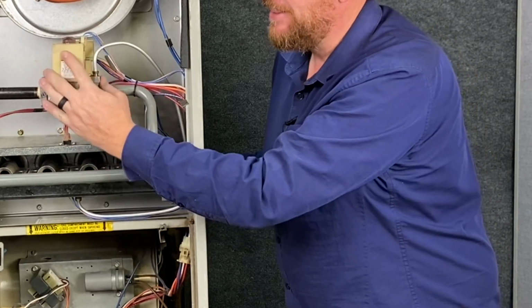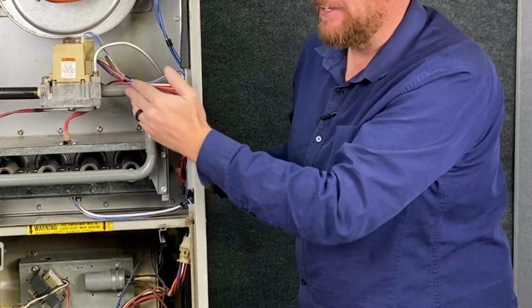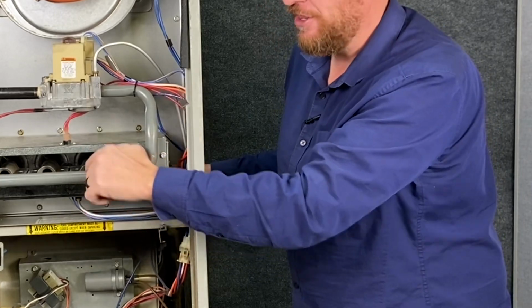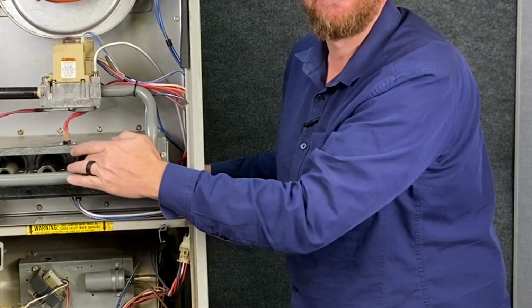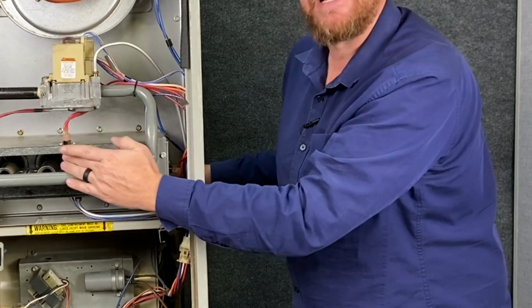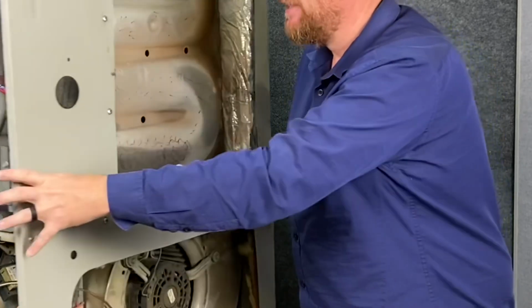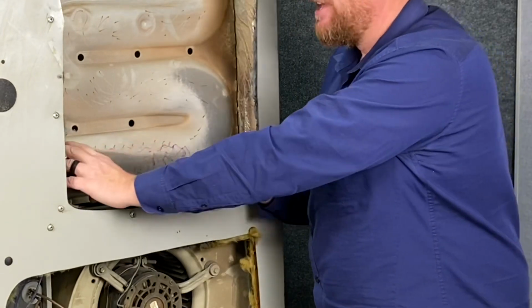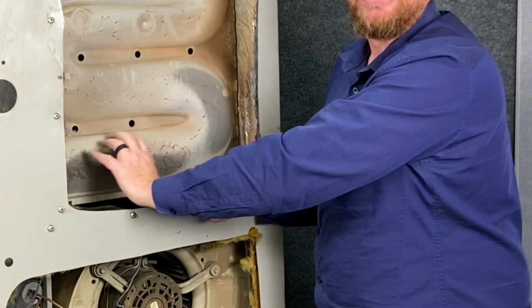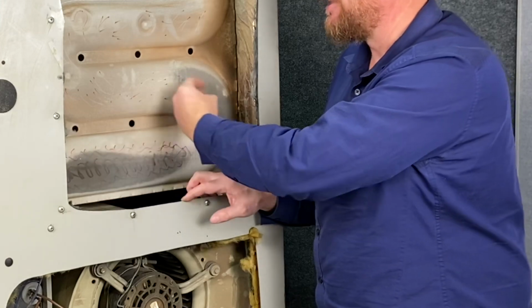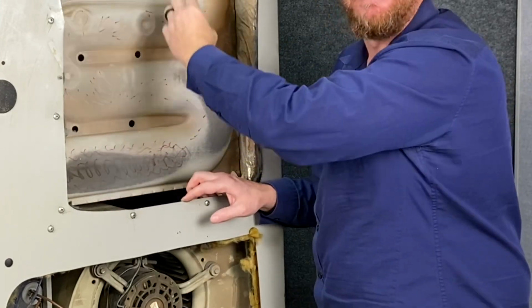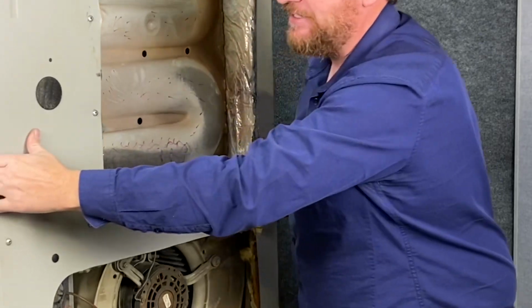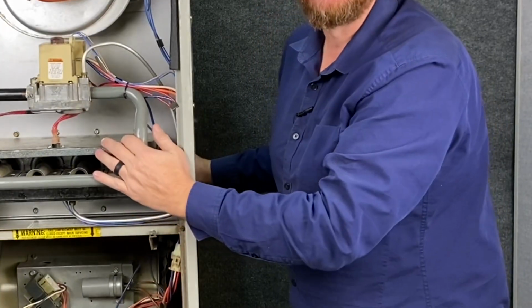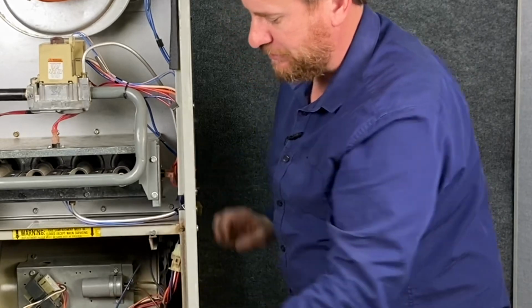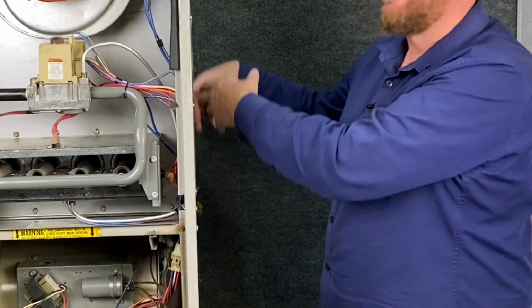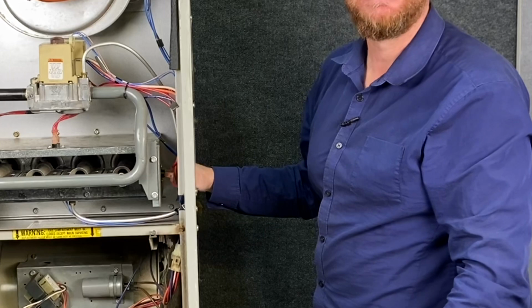Once that's proven, this valve is going to open the main solenoid, allow gas to flow through the manifold, to the spud, through the orifice, mixing with primary air in the jets or the burners, across that pilot light, igniting into a flame that's going to be burning inside of our heat exchanger. The flame is going to be burning in this section of the heat exchanger, which is our combustion area. Then it's going to be the hot gases traveling all the way out, being pulled by that inducer fan motor. The IFC is going to let this heat exchanger heat up. Then the IFC is going to energize our main blower, allowing us to move air across this heat exchanger and putting that heat into the house.